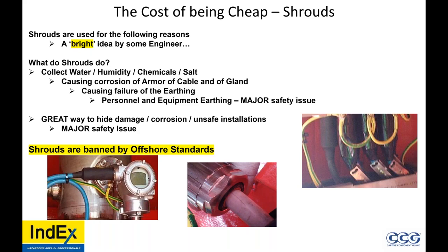If you look at the center picture, that gland is extremely over-tightened. Anytime you see the black on a hot gland, it's over-tightened. There's also a cut in the insulation. No cable testing was done, but they put the shroud on and they hoped that nobody would find it. Now, how do I do inspections or check the gland on this one on the left? That metal cable tie is in the way. Shrouds are really inflexible. How about this one in this junction box? For initial detailed inspection, brand new installation, I'm supposed to do 100% inspection.